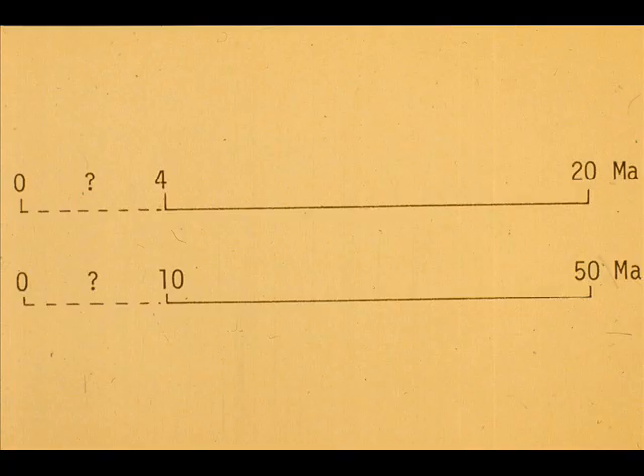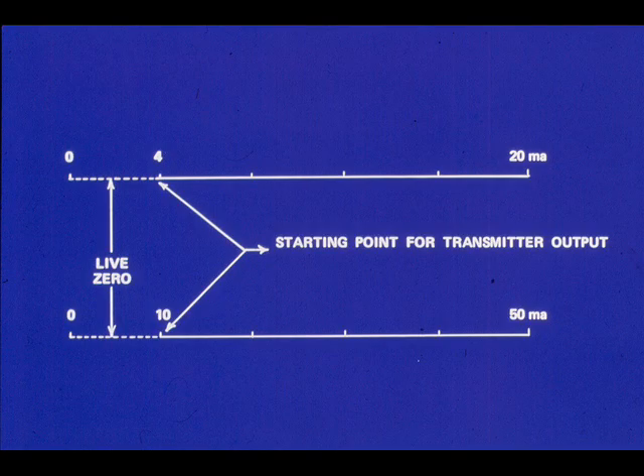Why did the output ranges not start at 0 milliamps instead of 4 or 10 milliamps? The reason is to get a live zero. In this way, if the transmitter output is too low for the low end of the range, the receivers will read below zero.